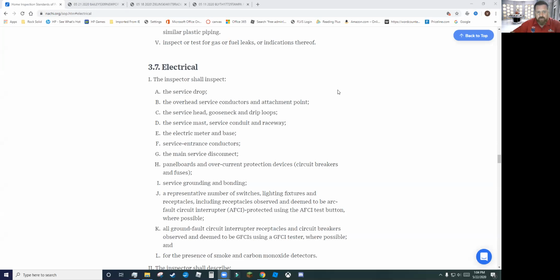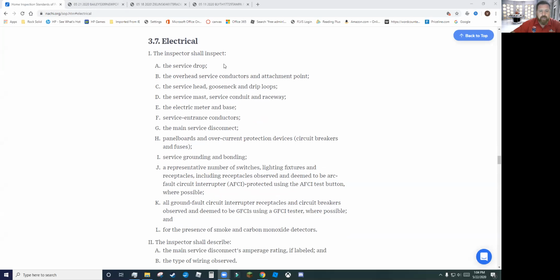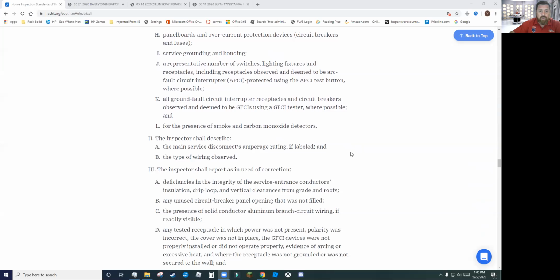Now, the standards of practice as set forth by InterNACHI are a baseline. At its most basic, the inspector shall inspect the service drop - that is the wires between the electrical mast and the meter - the overhead service conductors and attachment point, again at the mast, the service head, goosenecks, and drip loops, all mast related, the service mast, service conduits and raceways, the electric meter and base, service entrance conductors - that is the wires that go between the meter and the electrical panel - the main service disconnect, that's the main breaker, panel boards and overcurrent protection devices, meaning circuit breakers, service grounding and bonding, a representative number of switches, lighting fixtures and receptacles, AFCIs and GFCIs too. We're also going to look for the presence of smoke and carbon monoxide detectors.